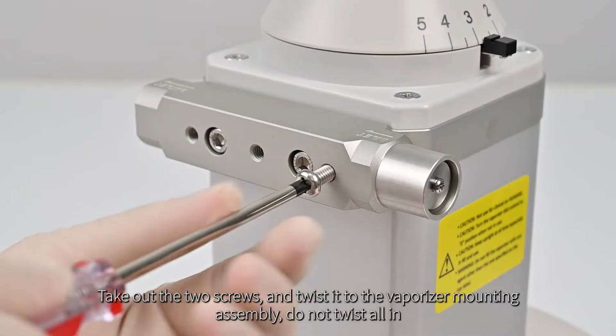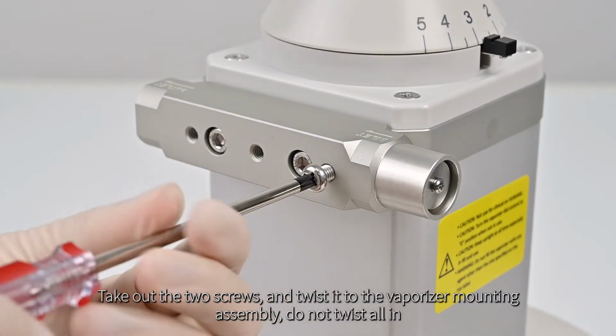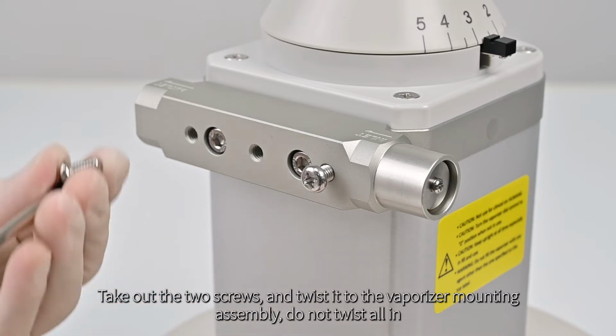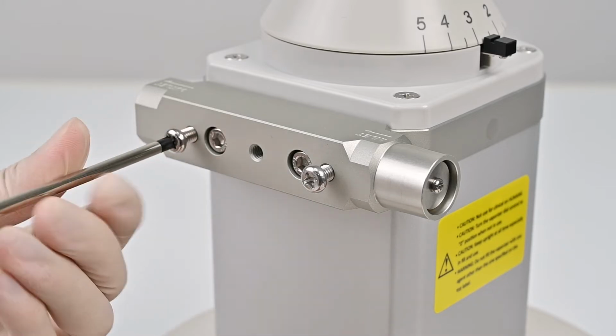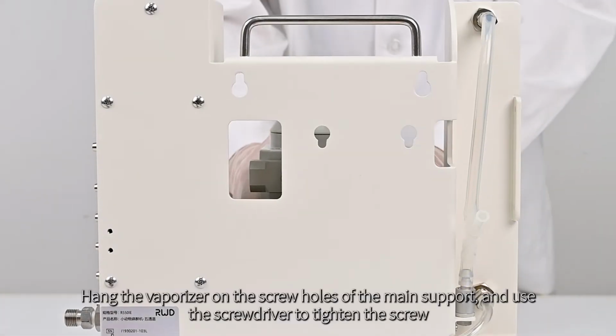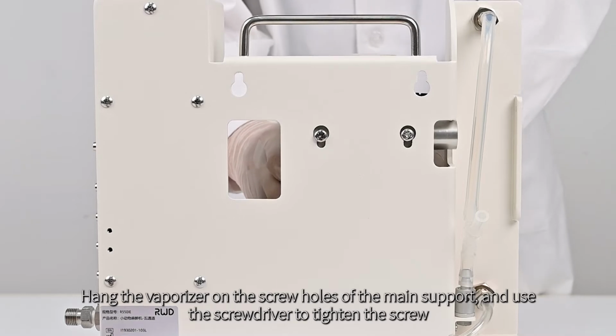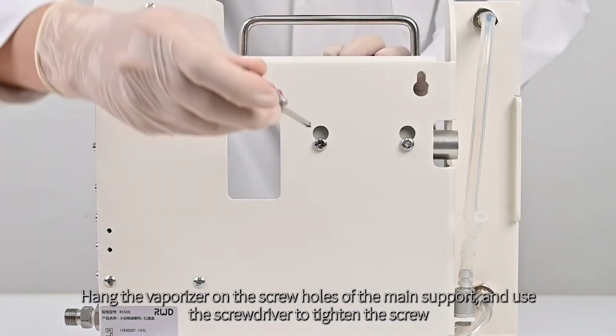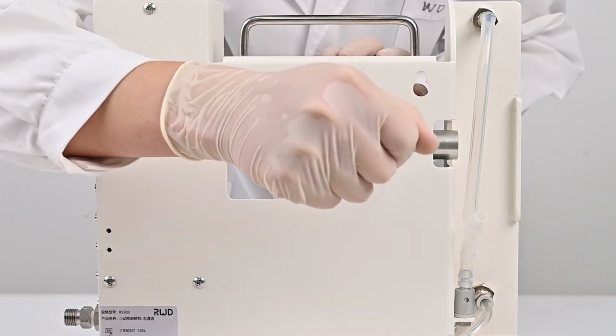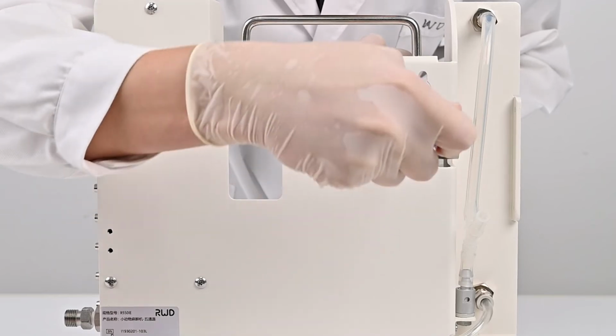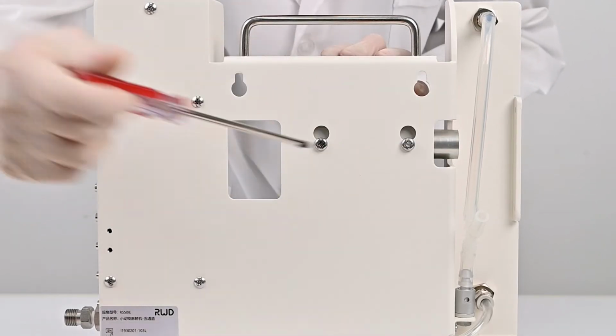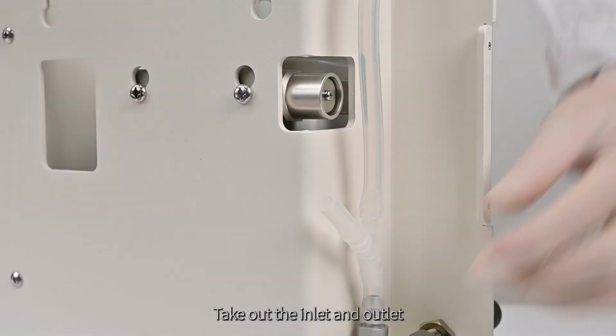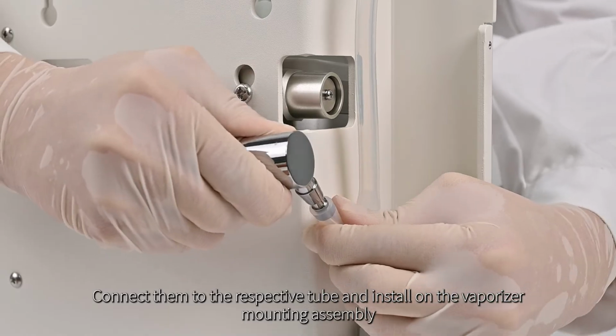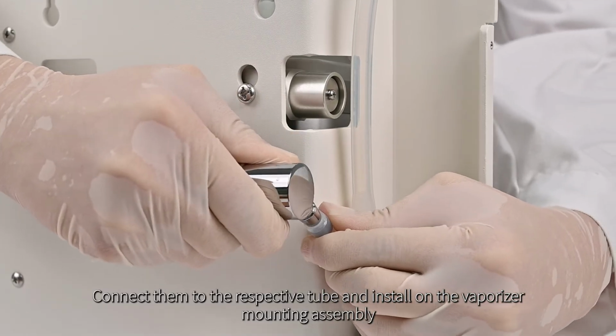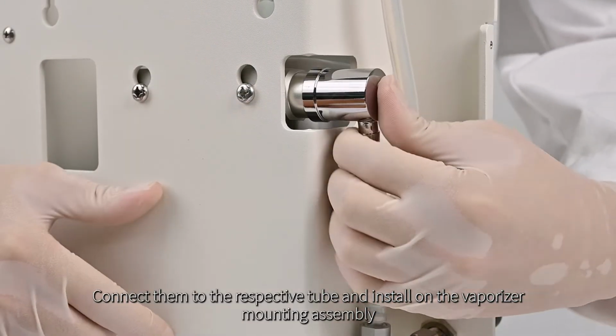Second, anesthesia machine installation. Take out the two screws and twist it to the vaporizer mounting assembly. Do not twist all in. Hang the vaporizer on the screw holes of the main support, and use the screwdriver to tighten the screw. Take out the inlet and outlet, connect them to the respective tube, and install on the vaporizer mounting assembly.